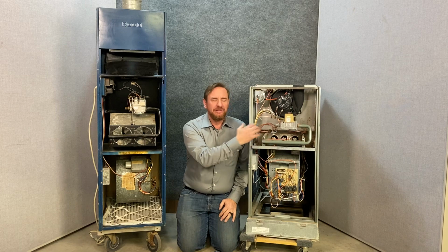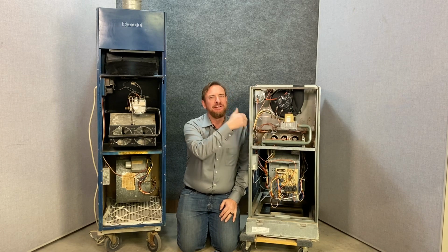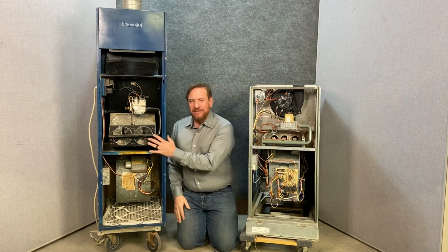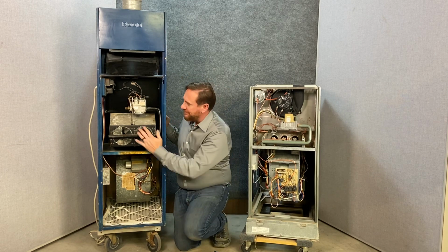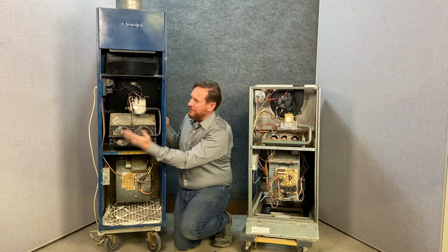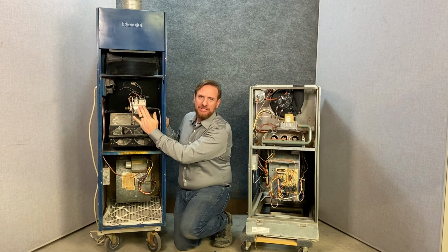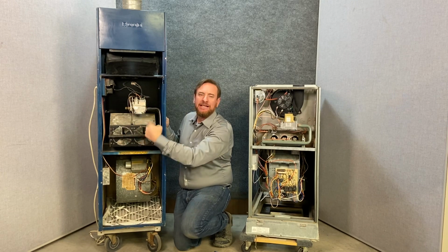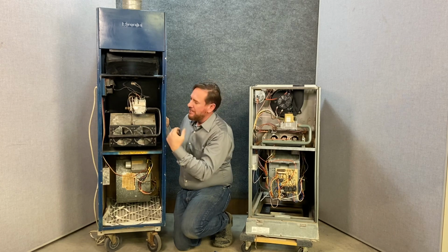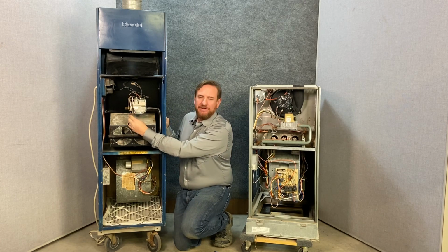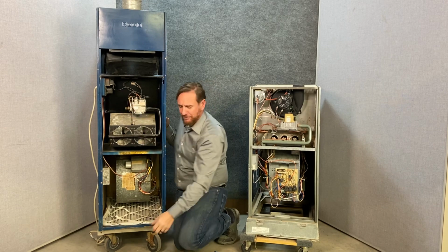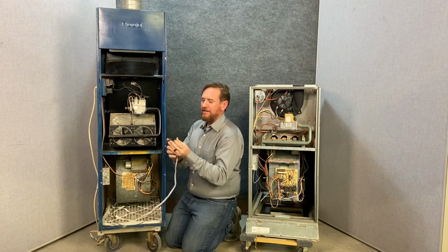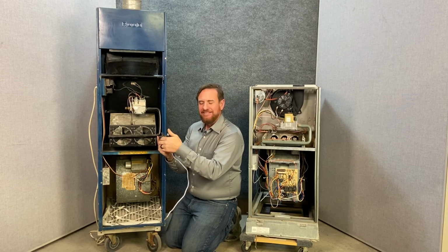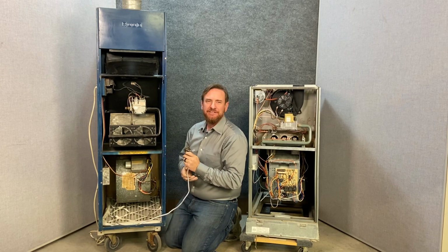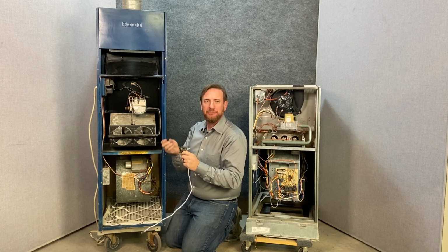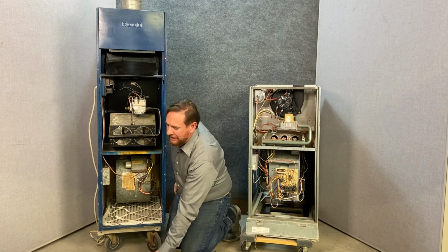We're trying to burn gas, mix it with air in the correct amount, and draft it out. This one, though, is significantly different in how it's done. The standing pilot's going to burn all the time. When a thermostat calls for heat, it just energizes this combination gas valve. Gas comes across that pilot, ignites into a flame, burning in that heat exchanger. The pilot lights were notoriously blown out, and you had this one safety called a thermocouple. A thermocouple would be right next to the pilot, and the pilot would burn against it, and that's its only real safety feature. If the flame blew out, the thermocouple would cool off and keep this combination gas valve from working.